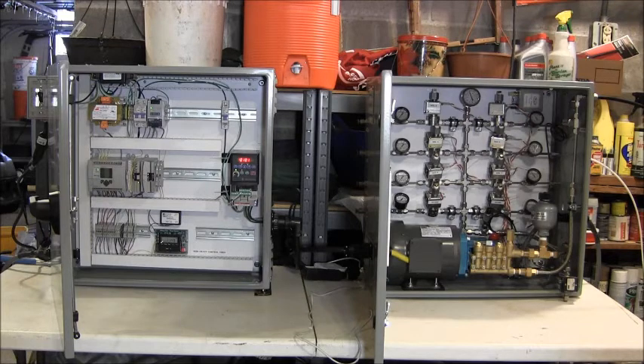But within this device there are some override features, or manual control features, and one of them is this timer right here, and the other two are these toggle switches right here. There are two toggle switches. You can see that one is on and that one is off, and those are override toggle switches. When you toggle one on, it brings on 3 of the solenoids for output. You toggle the other one on, it'll bring on the other 3 solenoids for output. So combined with this timer, those are a manual control operation. Within the microcontroller itself, we can utilize some automatic control operation with a PC interface, which we'll demonstrate in a little while here.